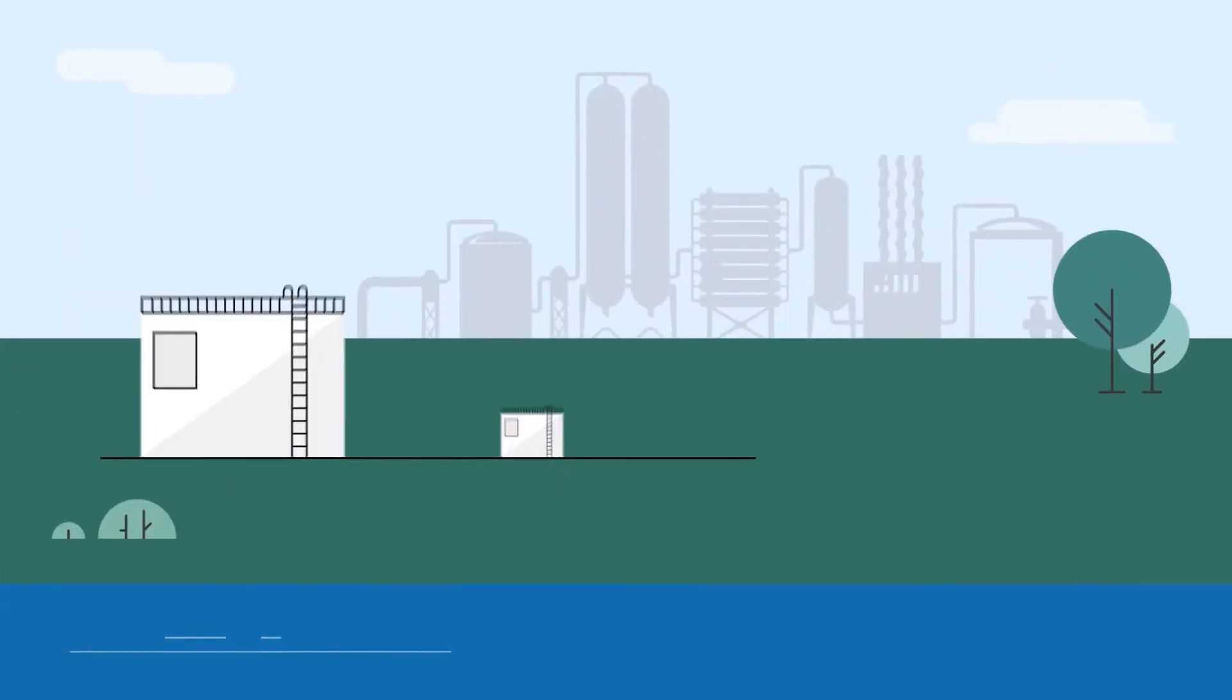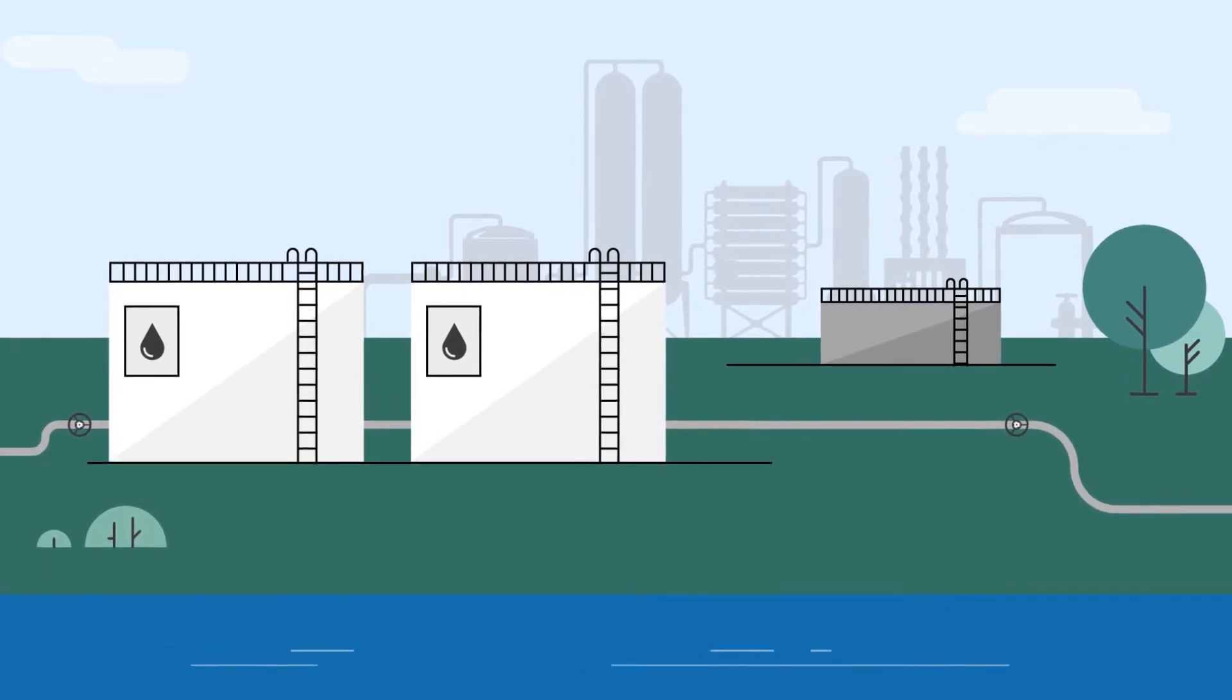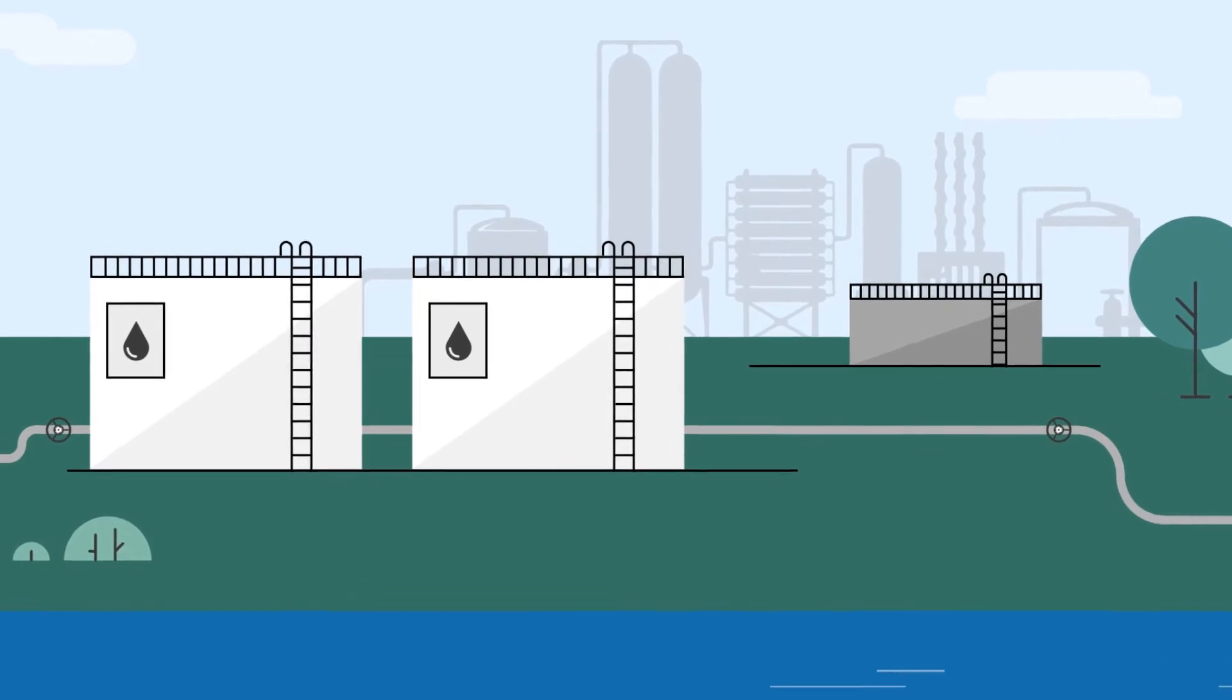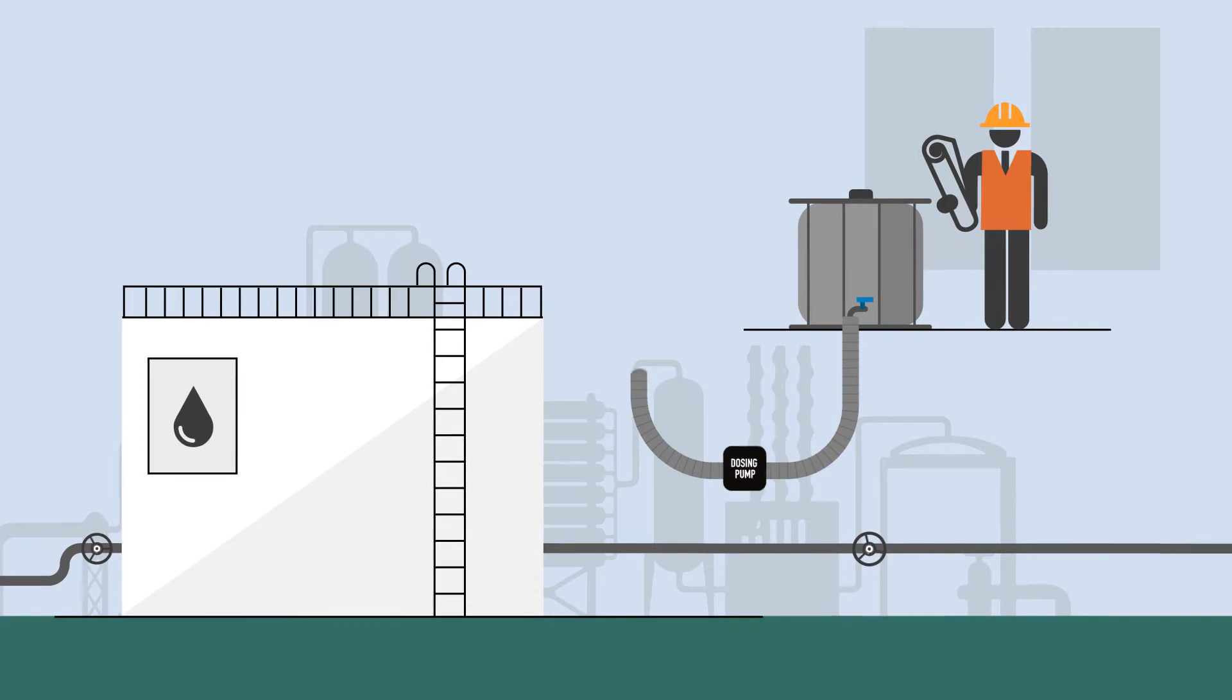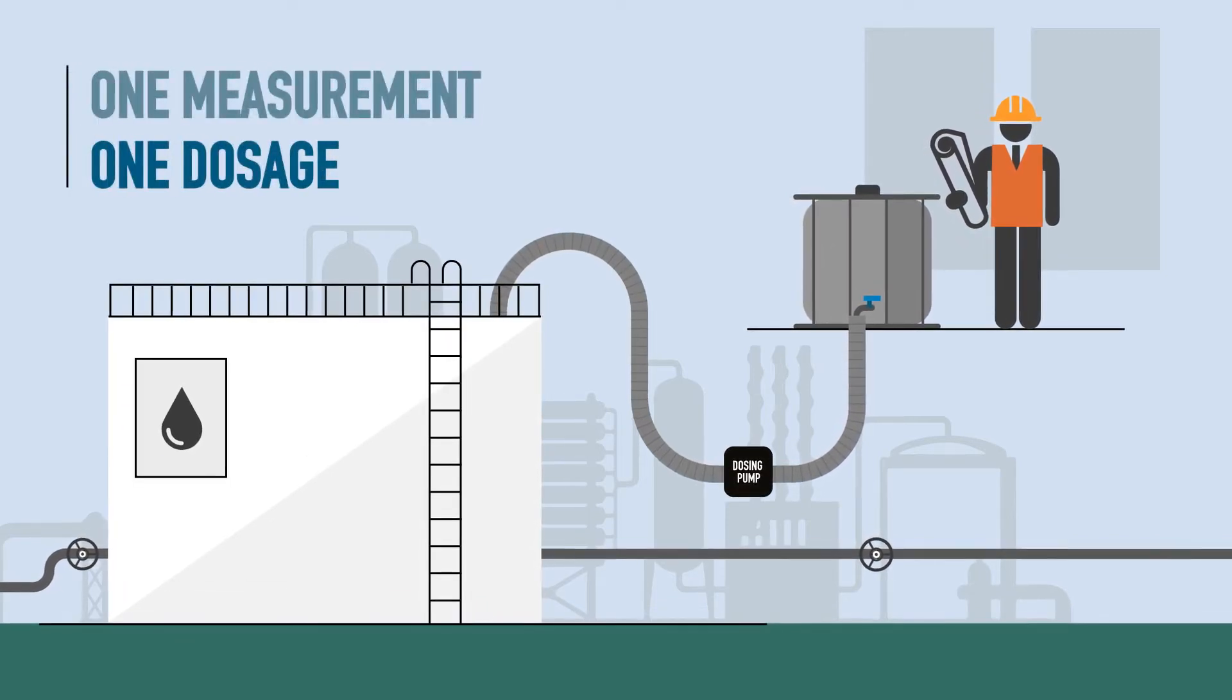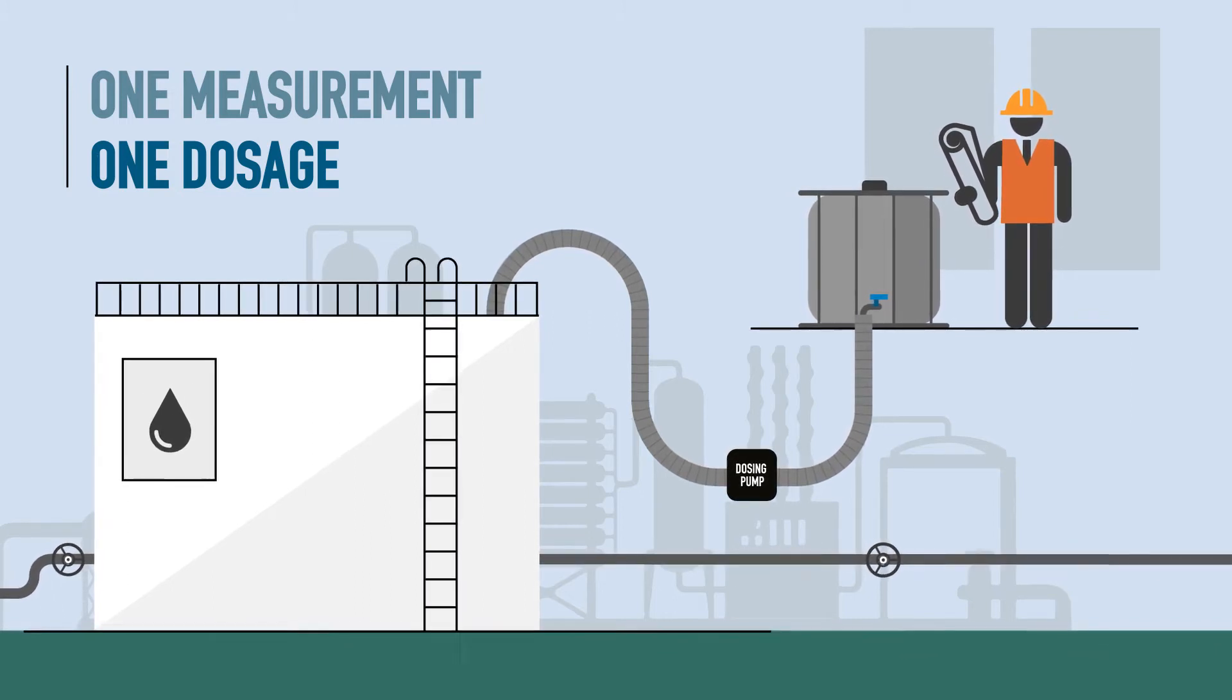Traditionally, industrial wastewater treatment systems usually control the dosage of chemical according to a turbidity measurement performed at the outlet of the sedimentation basin. That means after the sedimentation process and results in a considerable time delay in the chemical dosage control as compared to the changes in the water quality at the inlet of the process.